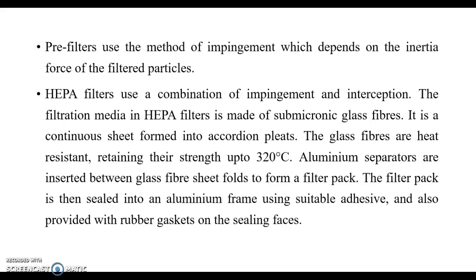This filter is made of submicronic glass fibers, and aluminum separators are inserted between the submicronic glass fibers. These fibers are heat resistant, retaining their strength up to 320 degrees Celsius. The filter pack is sealed into an aluminum frame using a suitable adhesive, also provided with rubber gaskets on the sealing faces.